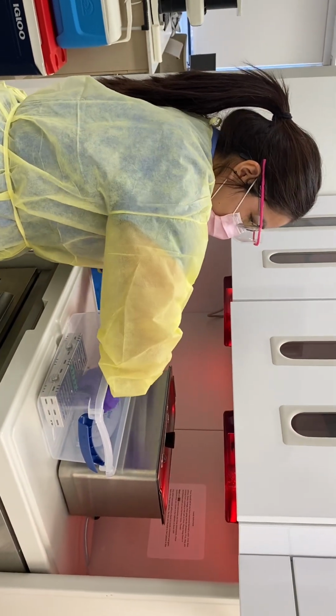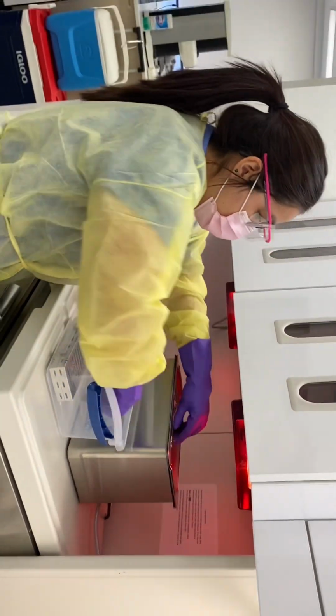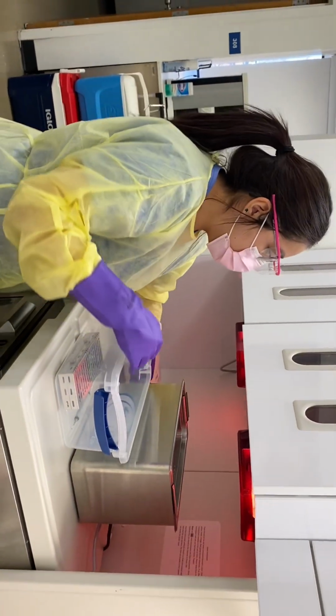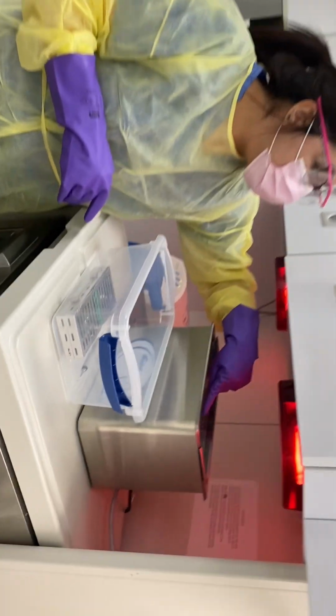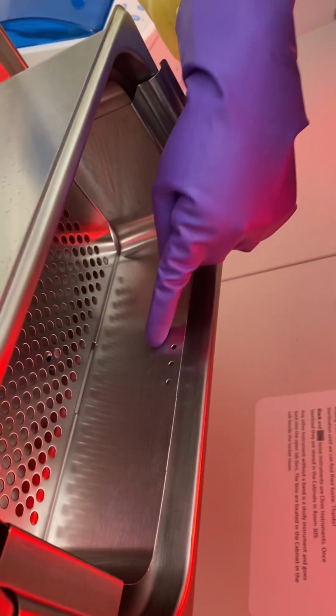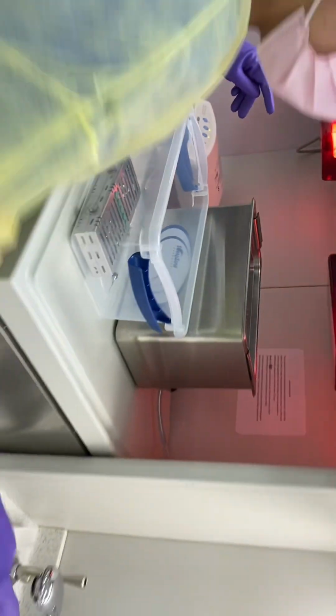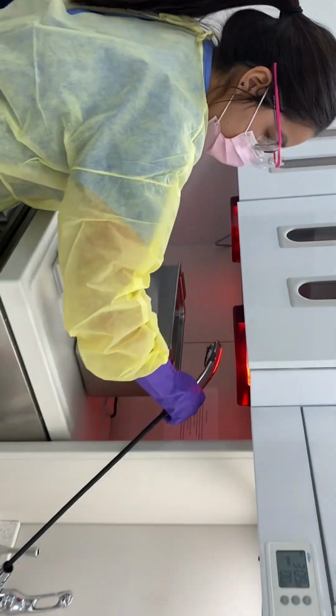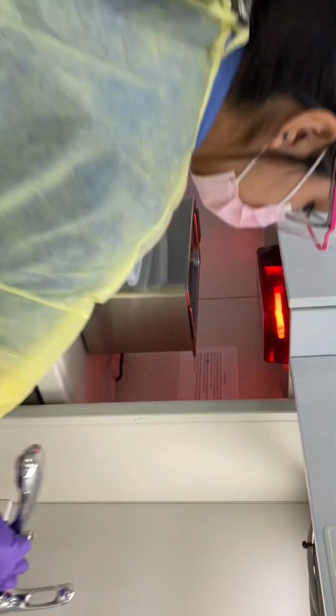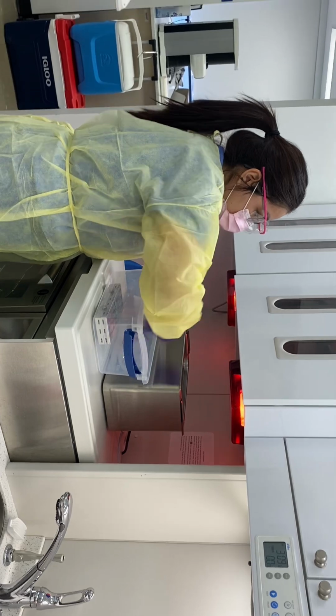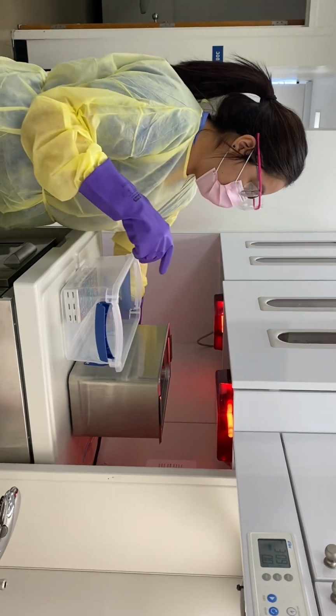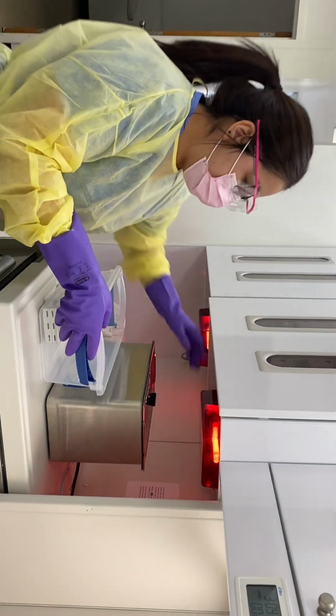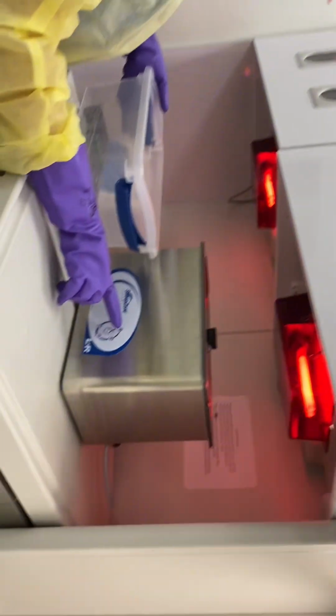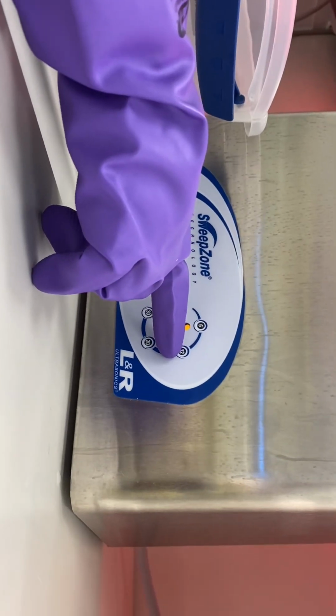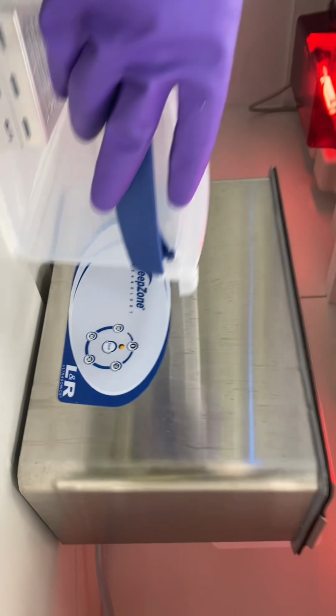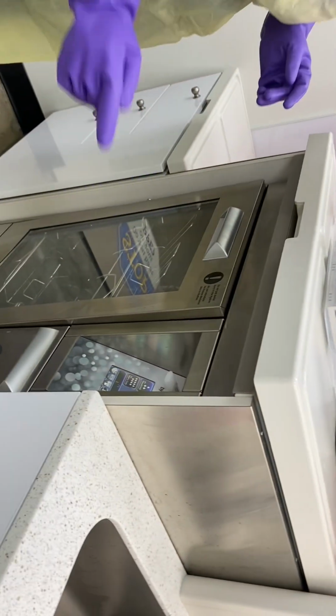Now we're going to do our loose instruments, which go in the ultrasonic. We're going to open our lid and make sure there's plenty of water. We want to make sure that there's water under those 3 dotted lines. We are going to add more water if we need by using the sink hose. We are going to put our instruments inside and run a cycle from 6 to 12 minutes, and we're going to hit our timer button.